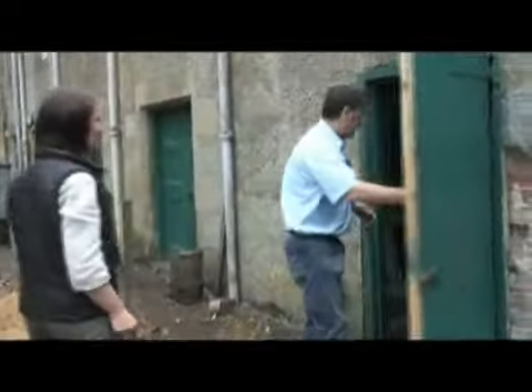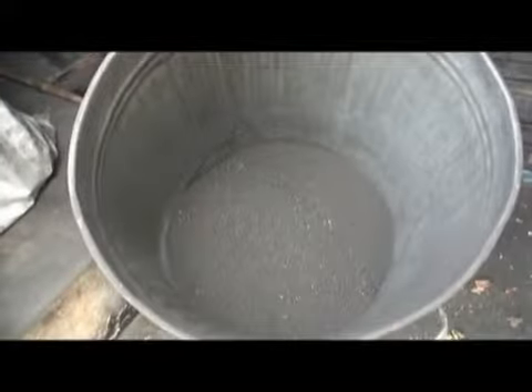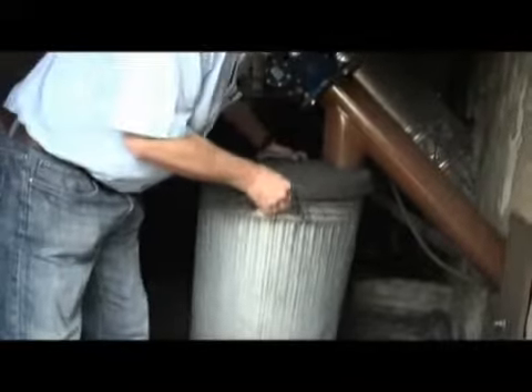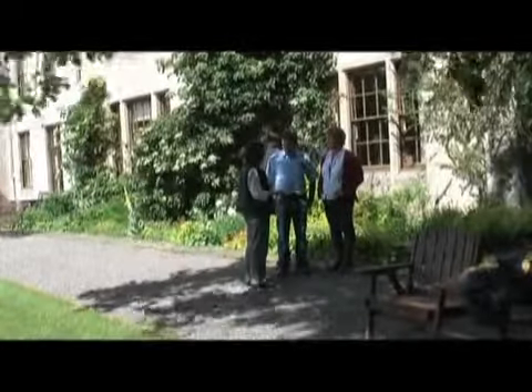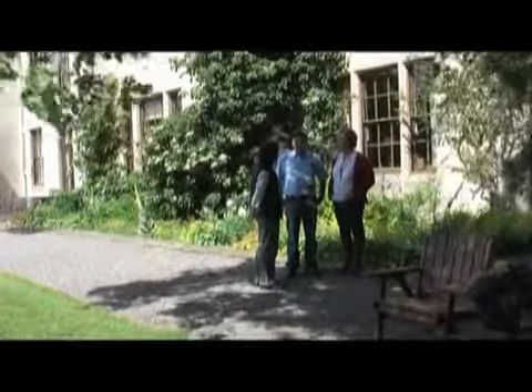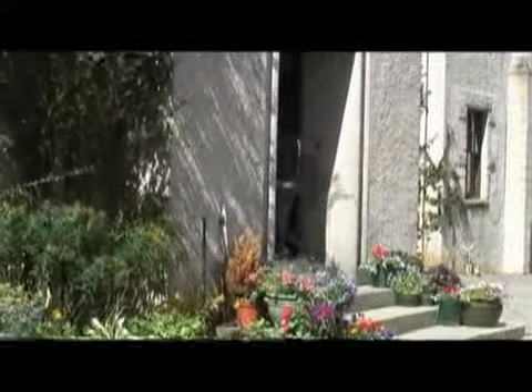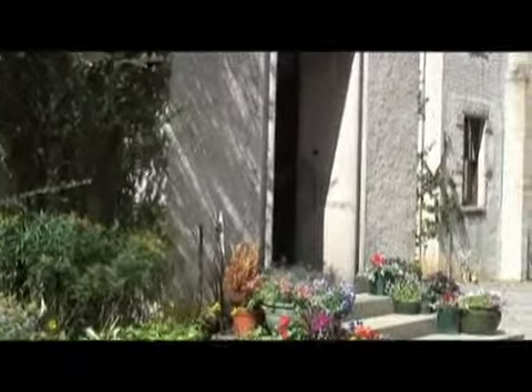This is the ash — I empty it about every two weeks. During winter, or if it's not running quite efficiently, I might empty it up to once a day. It's supposed to be 0.02% of the volume that goes in, so it's fairly small. The boiler mechanism itself was about £17,000, but by the time we'd changed all the plumbing and built the hoppers, the total cost was around £80,000, of which we got a 50% grant.